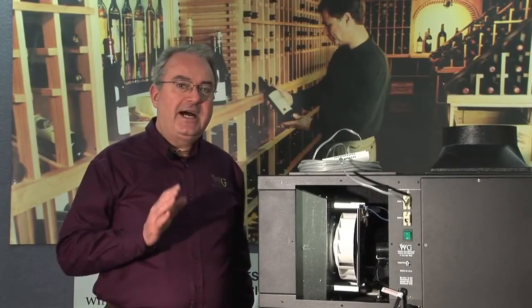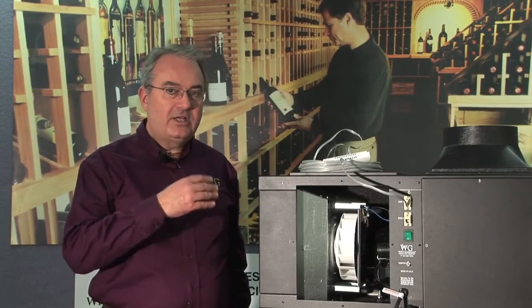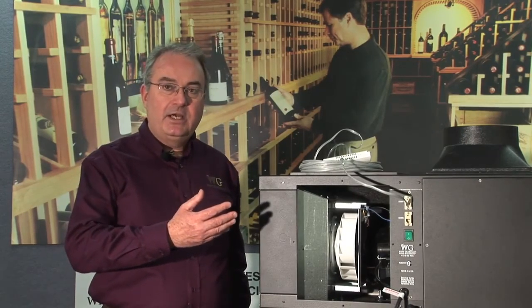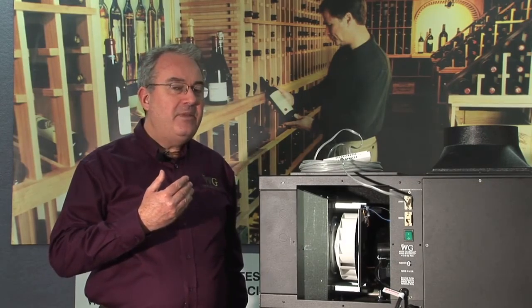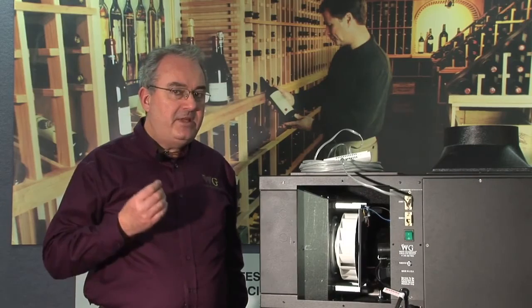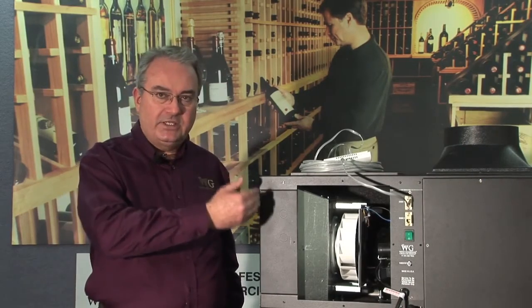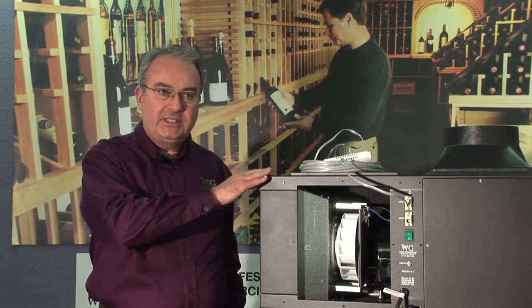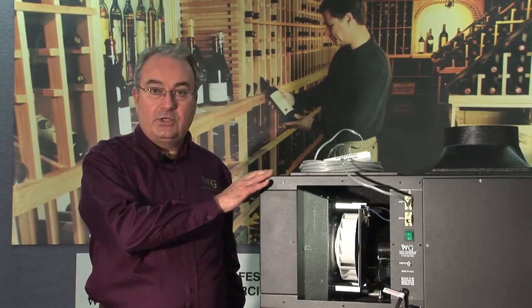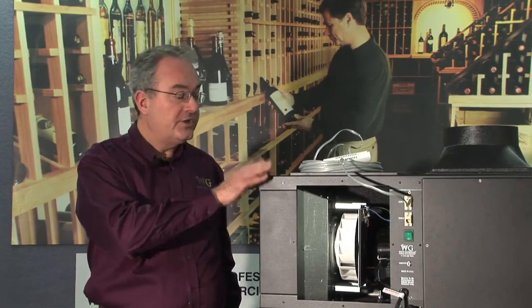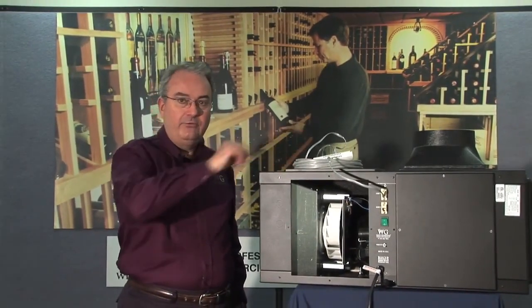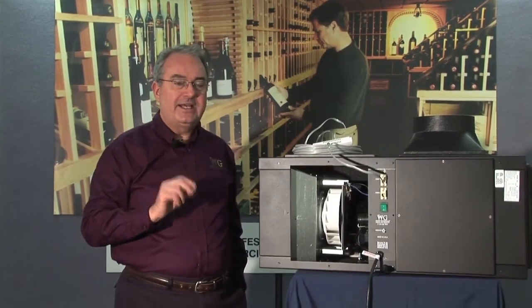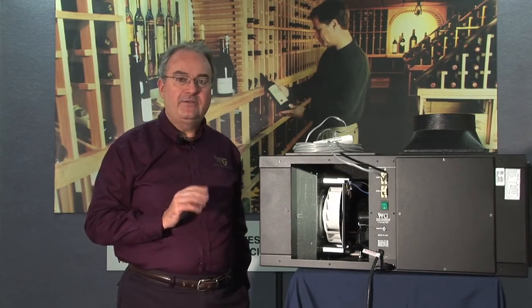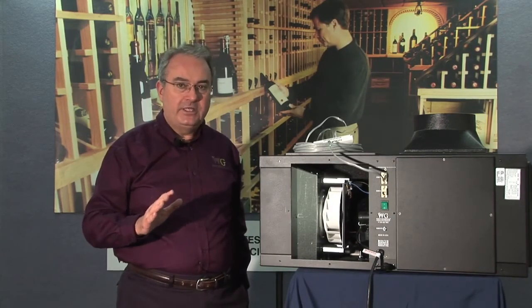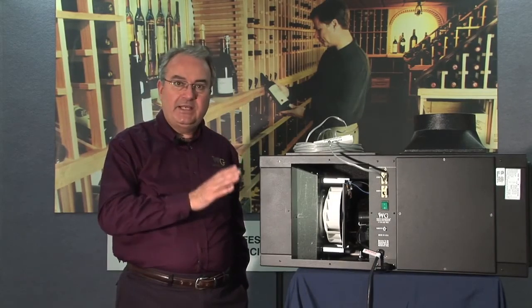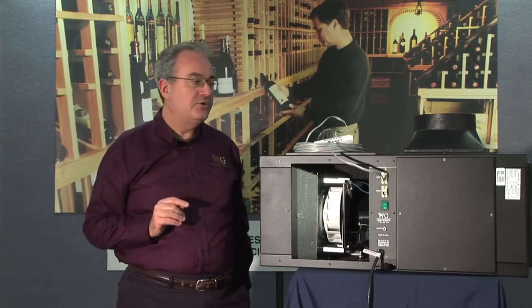Now the WineGuardian ducted unit is highly flexible. You have many options for the ductwork. We've talked about having 2 or even 3 supplies to the wine cellar. We talked about the length of the ductwork, but there are many other ways the unit can be used. They may not be the most common. Without doubt, the most common installation is to duct both the condenser and the evaporator, installing the unit in an adjacent space. But it is possible, for example, to install the unit outdoors. It's possible to put the entire unit outdoors and to duct the cellar air to and from the unit through the wall. If you choose to install the unit outside, it is essential that you shelter the unit from any kind of rain or snow. You have to have some kind of roof over the unit. This is not a unit which is really designed to withstand snow and rain. It can work outside, but it must not be exposed directly to the elements.